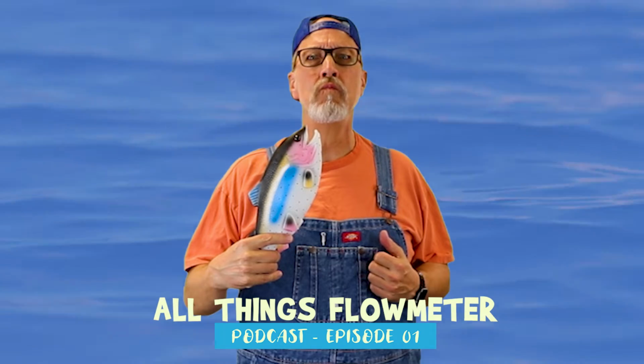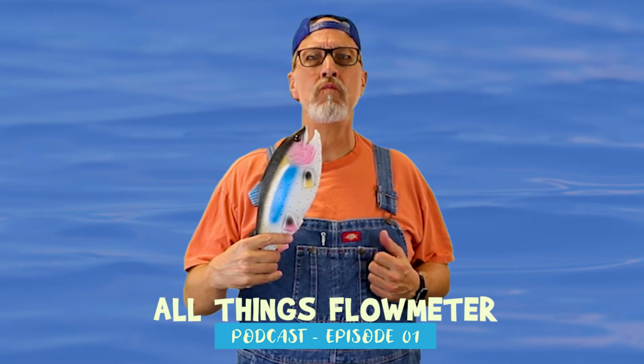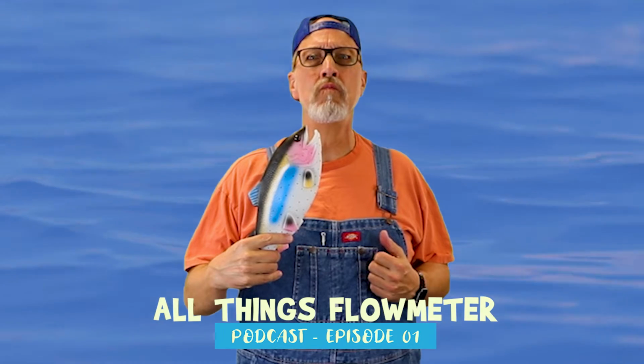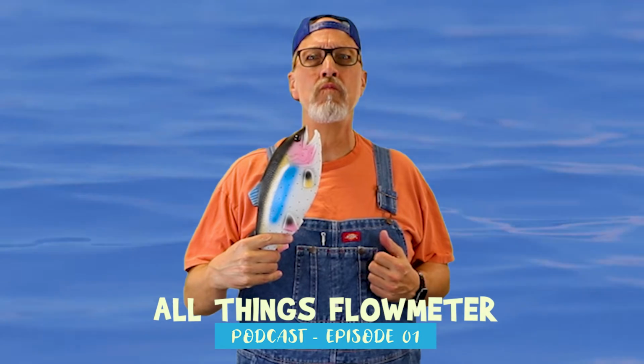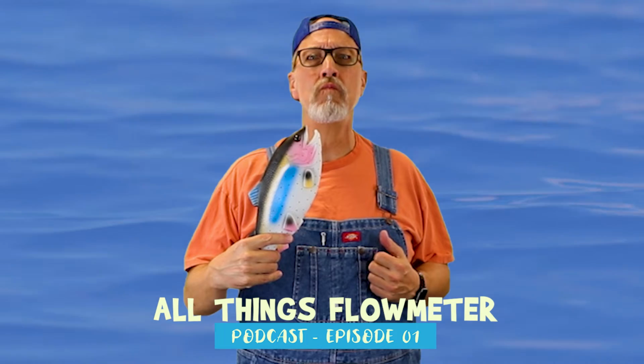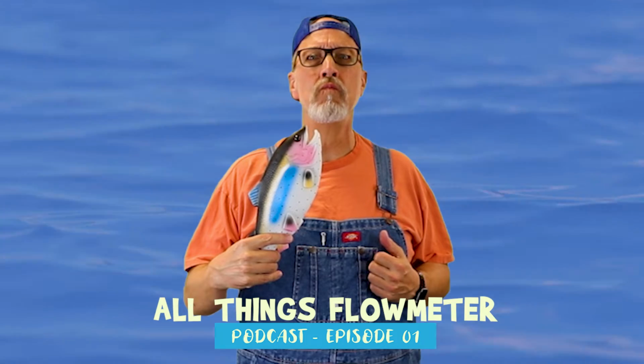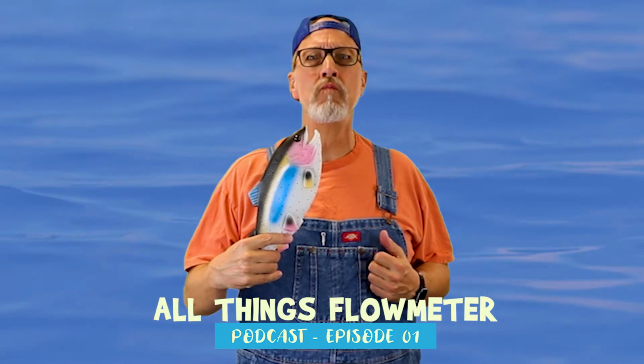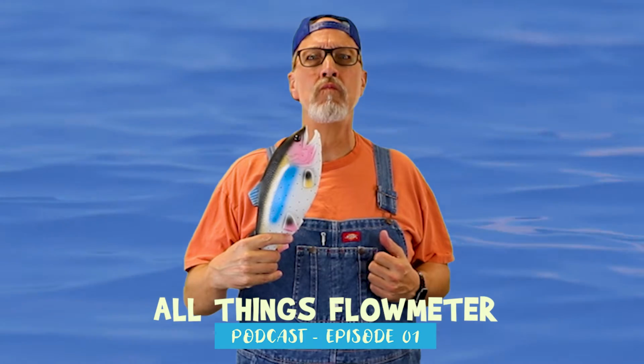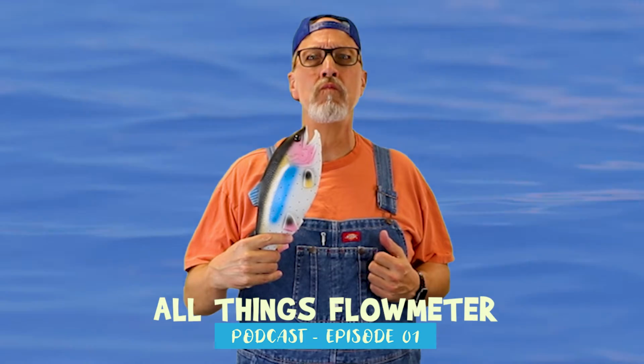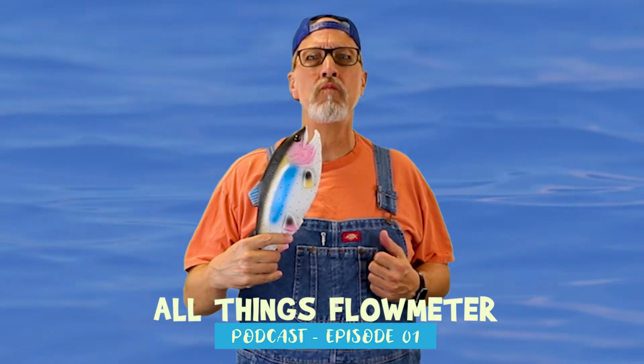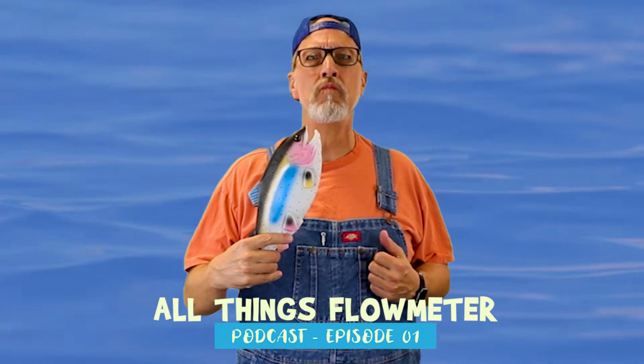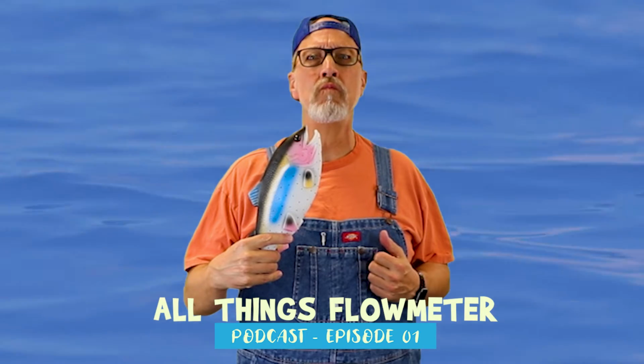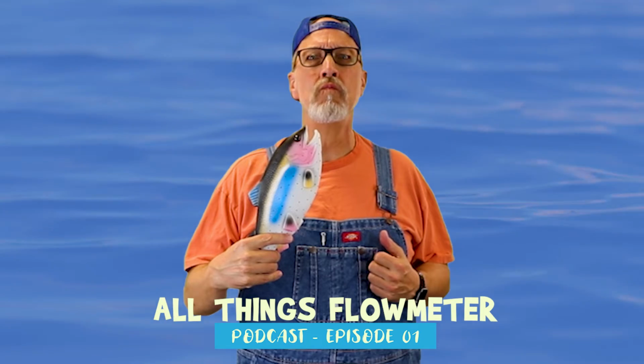That's the world that we're mostly in. But there are special equipments that can measure a line that's a 1/4 inch in size. So it's a wide variety. So it comes back to price and accuracy, what you're going to use. So in your world, in most cases, you're going to use a magnetic flow meter or an ultrasonic flow meter, in some cases a paddle wheel flow meter, if it's a low budget item, to tell you that I've got 100 gallons of water coming through here, and I've got to add this amount of ounces of this processed chemical to treat this water.